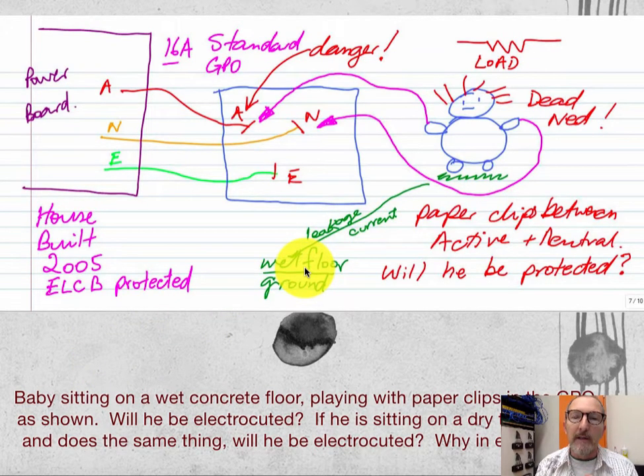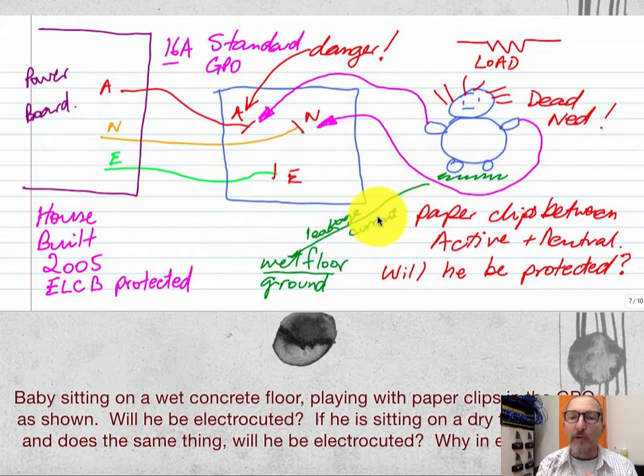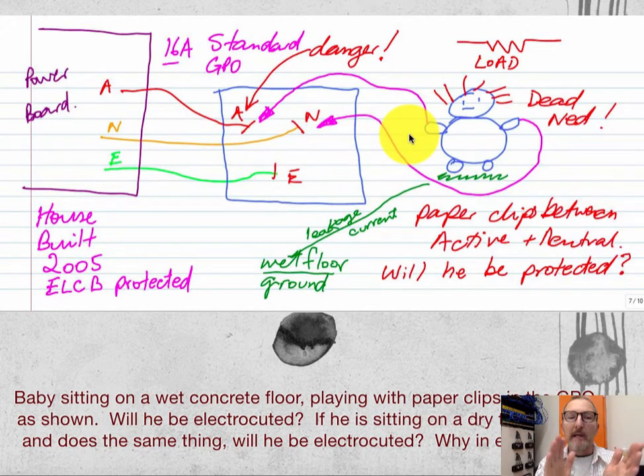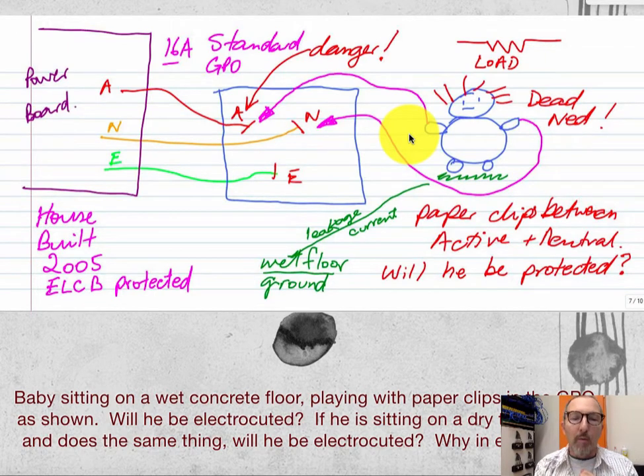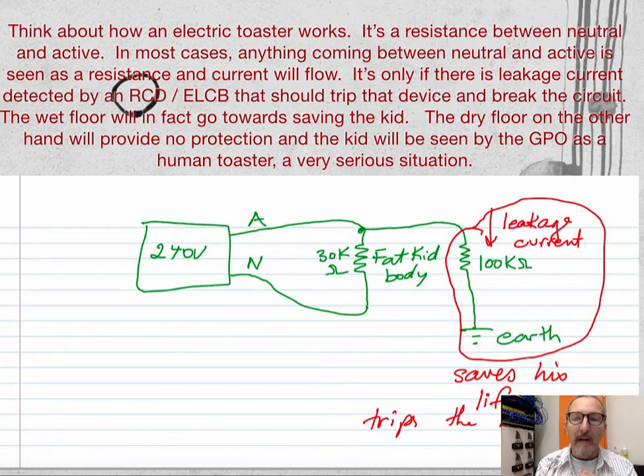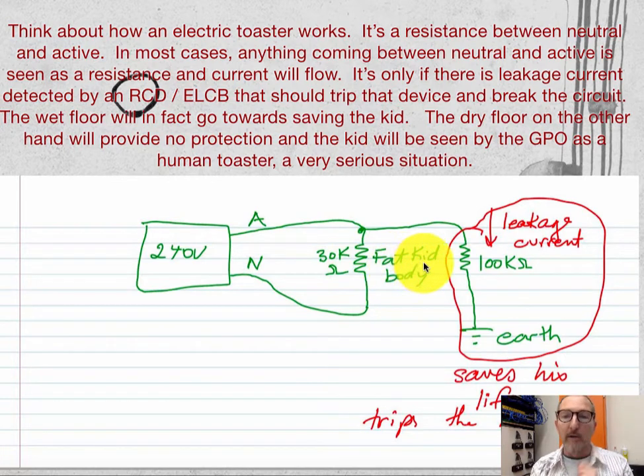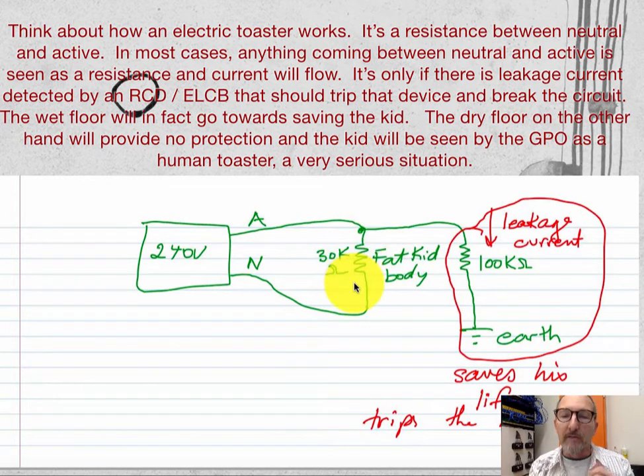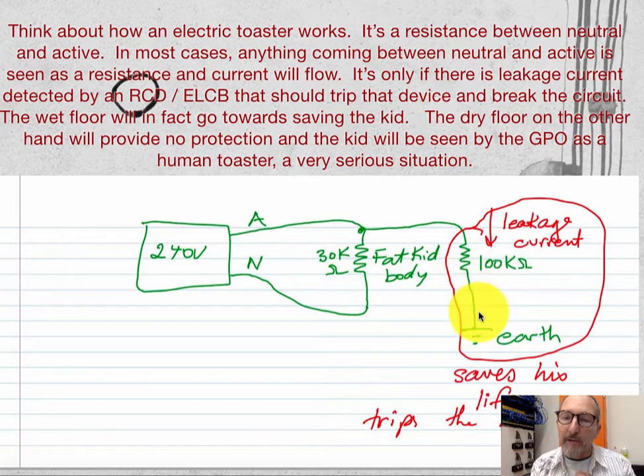He's sitting on the wet ground, so current is going to travel from the active through the kid's body and down to ground, with a different current going back through the neutral line. The RCD would trip and the kid would be saved. This robust kid sitting on the floor has a resistance of about 30,000 ohms in his body, and there's going to be a leakage current going down through his body to ground — and in that case, that's going to save his life.